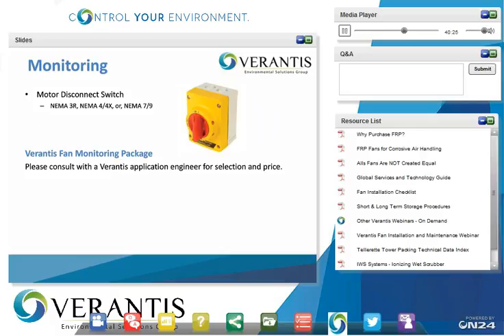Motor disconnect switch is a very important item that we recommend every motor be equipped with at least one type of disconnect, even if it's just a quick stop button. Based on the application of the fans, there are different types of disconnect. Could be NEMA 3R, NEMA 4 or 4X for weatherproof, and NEMA 7 or 9 for explosion proof. We do have packages for fan monitoring. So if you have any requirements for monitoring, please consult one of our sales or application engineers to make the selection for you.